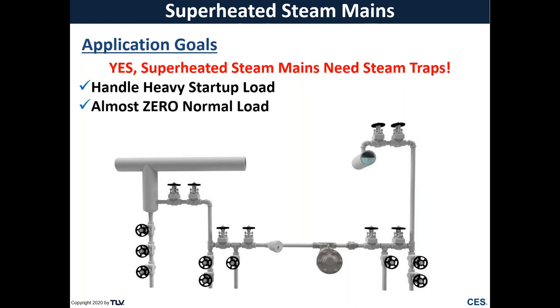Now during normal operation, you may see almost zero load, but there are conditions where you may see condensate due to upset conditions where you lose superheat or there's a sudden surge of condensate or something changes in your system. So you need to be able to adjust to those conditions.